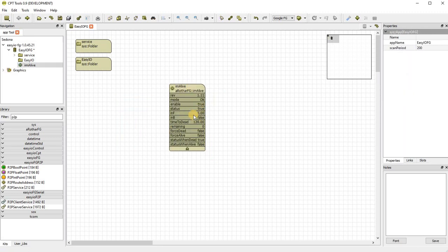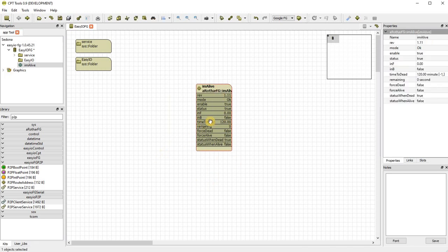So you can use a Boolean value for the in-B or a float value for the in-F. So if you've got a status, or if you have a point like a unit that turns on and off each day, you can put that into your in-B and set your timer up to be 12 hours or 24 hours. Rather than not knowing ever whether the thing's communicating or not, at least you'll know within 24 hours whether it's had a change of state or is working properly. So again, very useful for those sorts of things. The float is obviously the one we would use more often.